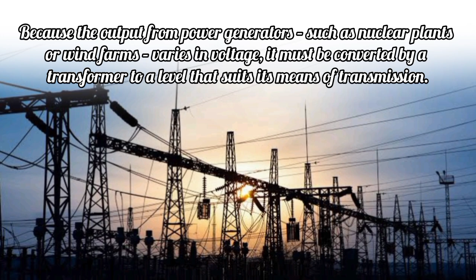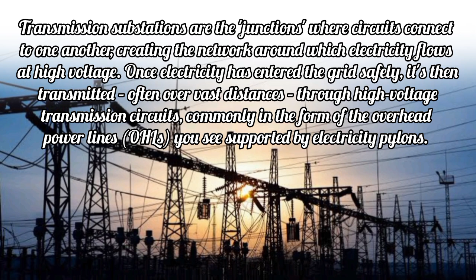Transmission substations are the junctions where circuits connect to one another, creating the network around which electricity flows at high voltage. Once electricity has entered the grid safely, it's then transmitted, often over vast distances, through high-voltage transmission circuits, commonly in the form of overhead power lines, OHLs, supported by electricity pylons. In the UK, these OHLs run at either 275 kV or 400 kV. Increasing or decreasing the voltage accordingly will ensure that it reaches local distribution networks safely and without significant energy loss.